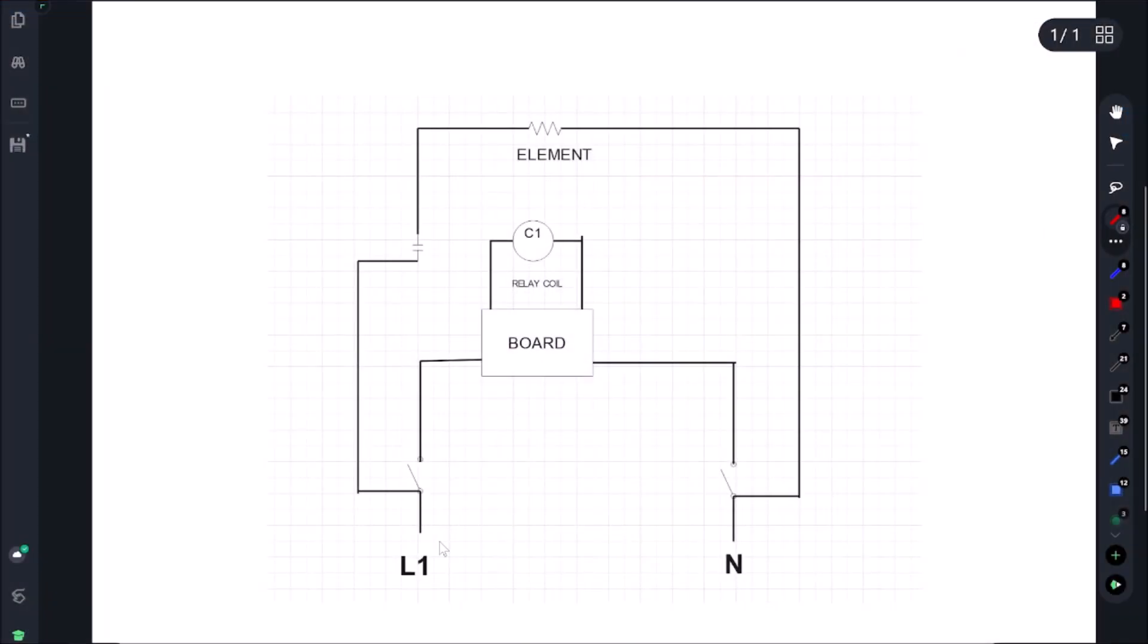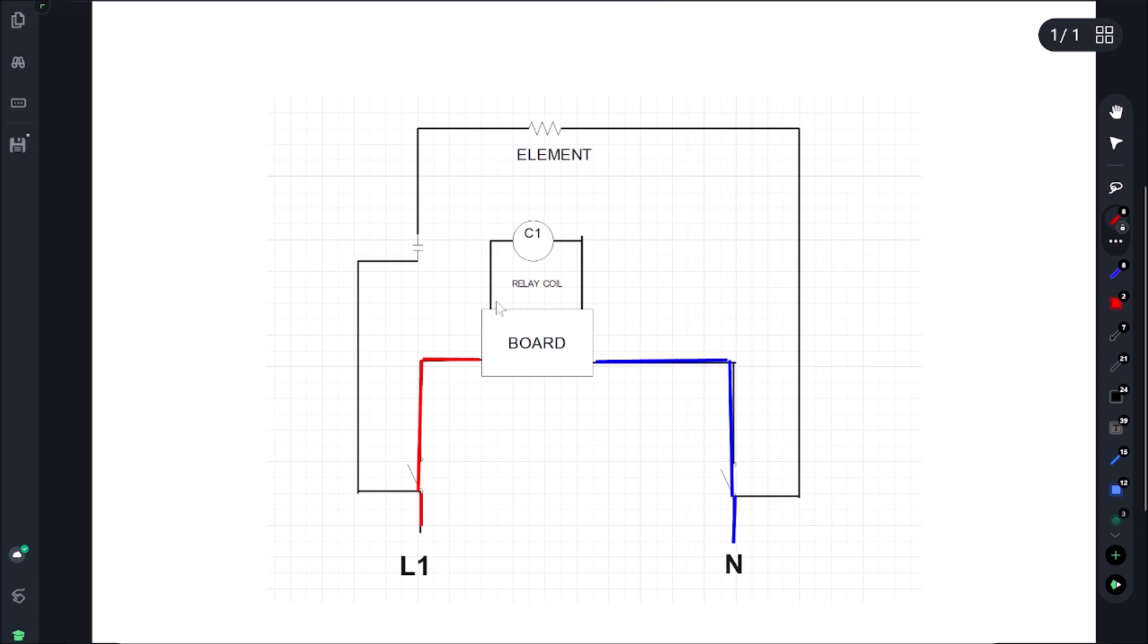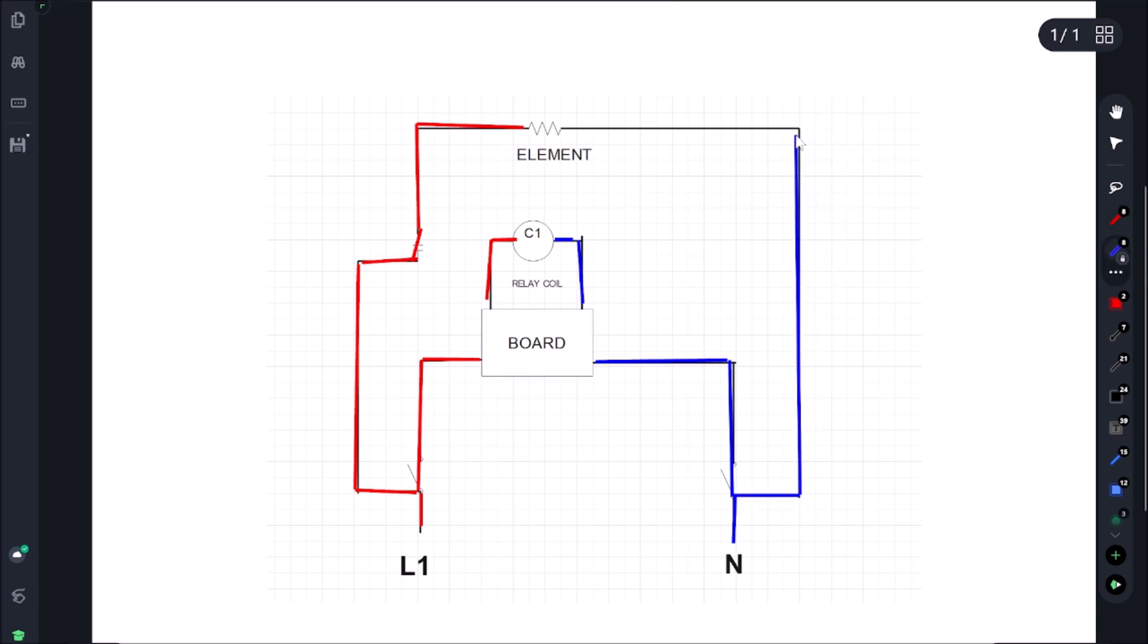Let's just go over our sequence of operations here. So we have power into our switch. Once our switch closes here, we're going to power up our board. So we're going to close both sides of the switch. The board's going to get power. Now the board has a temperature probe. When there's a call for heat, we're going to send power to our relay coil here. When our relay coil gets power, it's going to close this contact right here. So this is fed from the incoming side of the switch. We get power on our relay coil and then we have power on the element. Our neutral side is a straight shot from the incoming power on the power switch, the inlet side not the outlet side. There is a completed circuit. That is our sequence of operations.